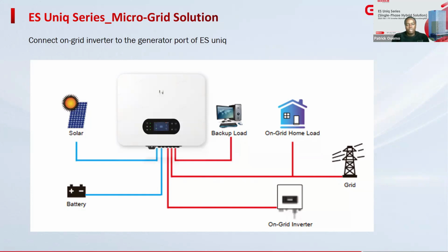Now, similarly, I mentioned that the ES Uniq comes with the diesel generator port. That port is not strictly for diesel generator integration. It's customizable. So the same port during commissioning, you can set it up to be an input from an on-grid inverter. On-grid inverter is a grid-tied inverter. Now that grid-tied inverter can be a GoodWe inverter or even a third-party inverter. But whenever the grid fails, the ES Uniq inverter can still control the grid-tied inverter so that they work as one to support the loads in the backup. Similarly, it can also allow the charging and discharging of the battery. So the system utilizes your grid-tied inverter, so it works as one, and it achieves the microgrid solution.